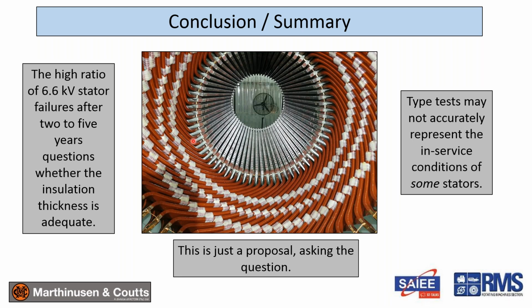And the question is just, this high ratio of failures, where does it come from, and why just on 6.6 kV? And is the fact that 6.6 kV insulation is based on the electrical stress maybe too far reaching? Should it not have some amount of mechanical allowance, as has been the case in the past? Back when I was at ABB many years ago, the limit we used for 6.6 kV was 1.6 millimeters. And then the second part is related to the type test, the thermal cycling elevated voltage endurance test. Is that really an indicative or representative test of real stators, especially ones with long core lengths?